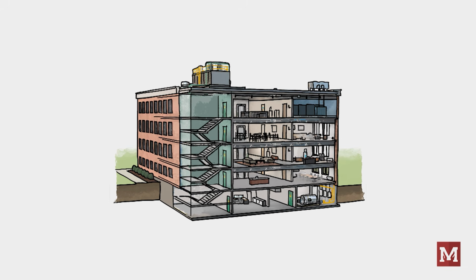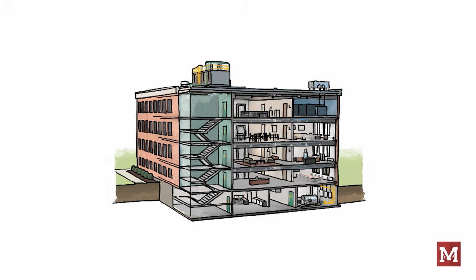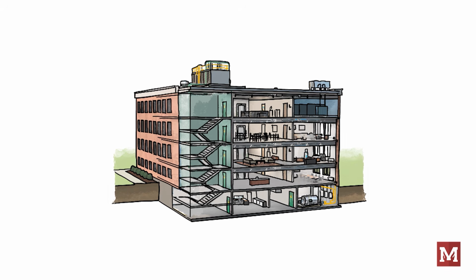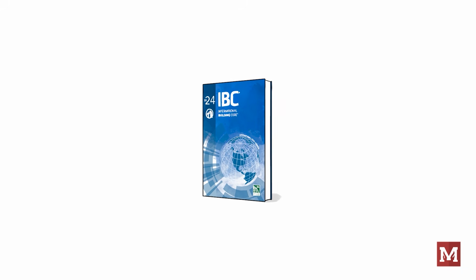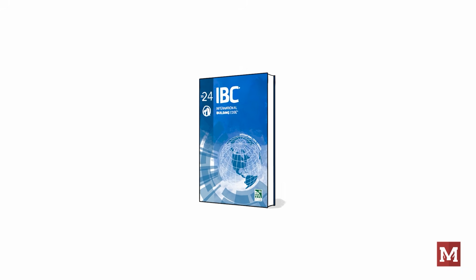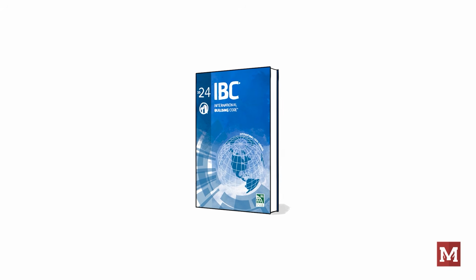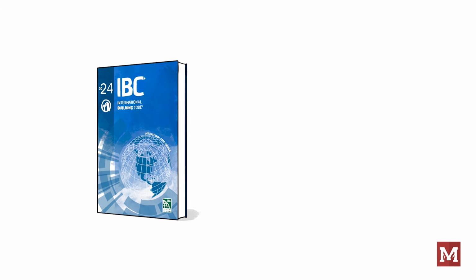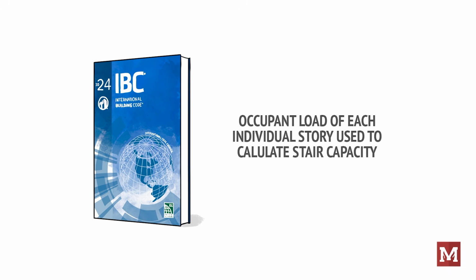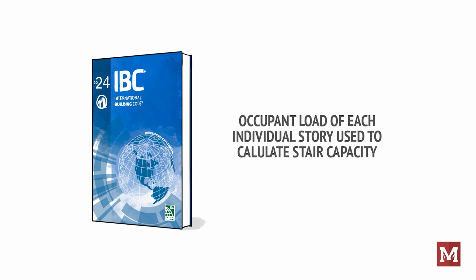Even though many buildings utilize a total evacuation principle, where all rooms and all occupants evacuate upon the fire alarm activating, typically each story is analyzed individually for its egress capabilities. In IBC, Section 1005.3 addresses the required exit capacity for rooms, area, spaces, or stories, meaning each story is analyzed individually. The interior exit stair considers only one story, in other words, not all stories at the same time.